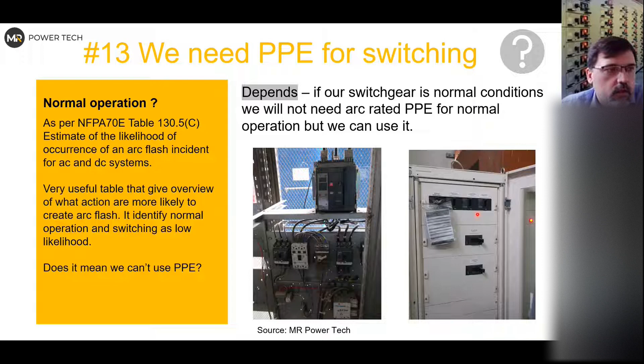But if you see the pictures that I took from one site, I think 2 sites, you will see that there is a difference between switching this breaker and switching here. And what you don't see here, there were copper bus bars on top of this one. So that's why I wear PPE every time I go on site. You don't see there were top bus bars with cables connected down to everything here. So for switching this one, you will need PPE because you will be directly exposed to the live copper bus bars. And if you look at this one, you don't need PPE.